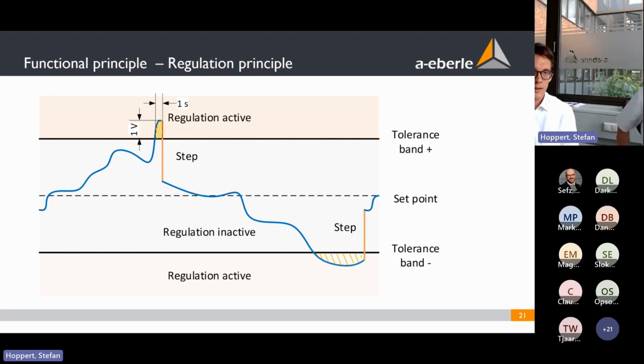For the regulation principle, here the blue line shows the voltage. When it's fluctuating, it goes up above the tolerance band. We want to make it as simple as possible. If it's above the tolerance band, then we step down. If it's below the tolerance band, we step up. So these 2 ways are possible. And for the regulation speed, or regulation time, how long it takes until it steps, this is a parameter you can set. Here, if it's 1 volt for 1 second, you multiply it, and then you get the regulation speed for 1 volt-second. So it should be quite simple. And normally with the regulation parameters, you don't have to set anything. The standard parameters work quite well for most applications.